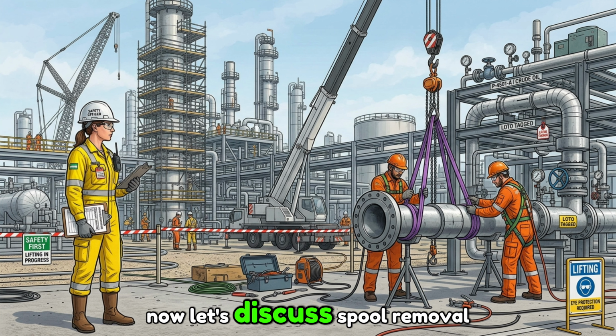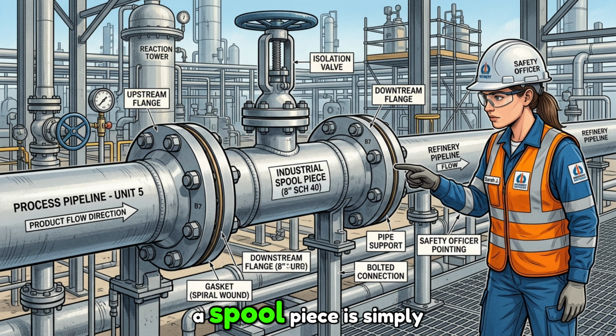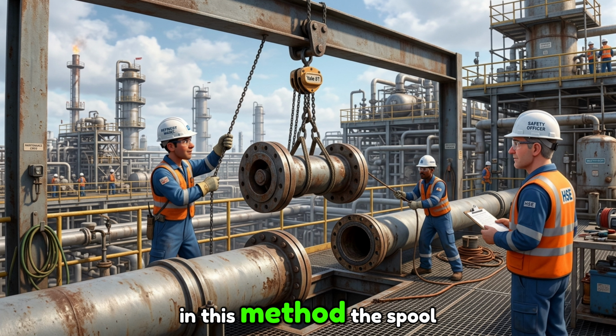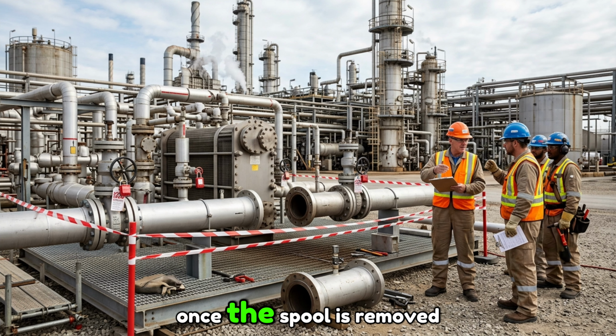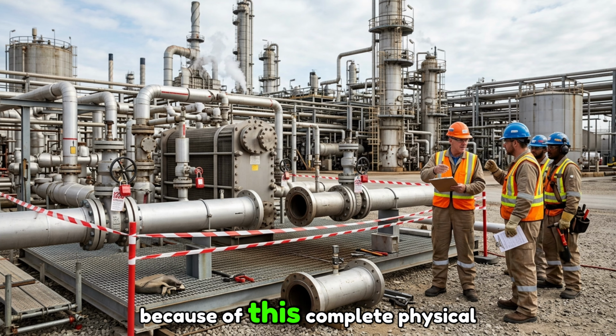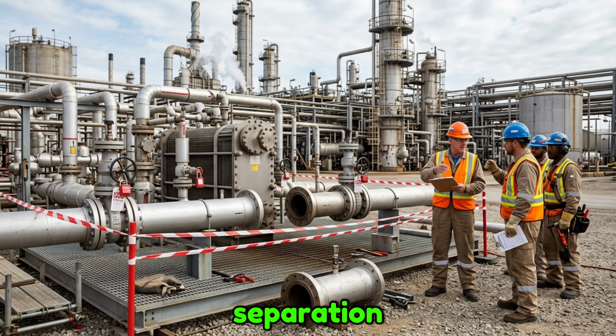Now let's discuss spool removal. A spool piece is simply a section of pipeline. In this method, the spool piece is completely removed, or a section of the pipeline is disconnected. Where required, the open end is secured using a blind. Once the spool is removed, there is no physical connection between the process line and the equipment. Because of this complete physical separation, spool removal is considered one of the safest and most reliable methods of positive isolation.